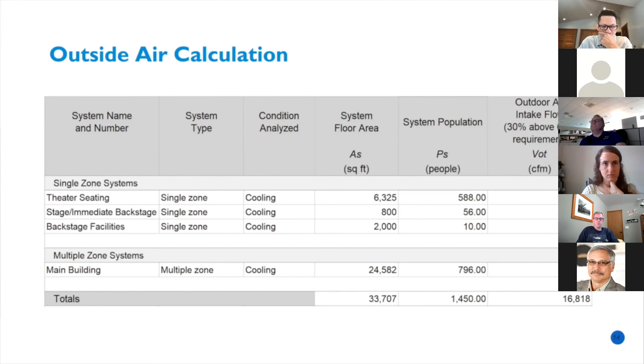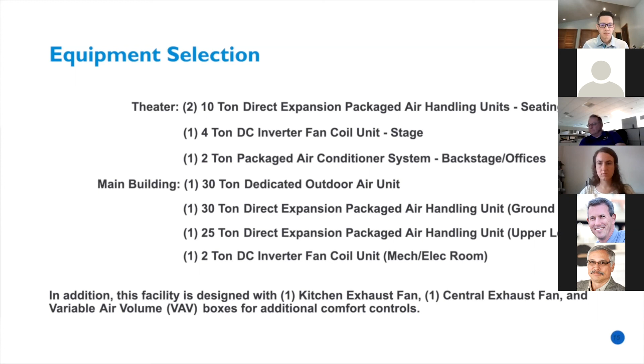The main building uses a dedicated outdoor air system, DOAS unit, to supply conditioned outside air. The remaining units were sized by subtracting the DOAS load from the total heat load and are broken up by level. We also included a kitchen exhaust fan, central exhaust fan, and variable air volume boxes for additional comfort controls. The main mechanical room holds the DOAS, the air handling unit, plumbing equipment such as boilers and chillers for water, and a connection to the outside via the louver. There's also a shaft, seen next to the elevator, to bring fresh air from the DOAS to the upper floor. This room is conditioned by a dedicated fan coil unit.